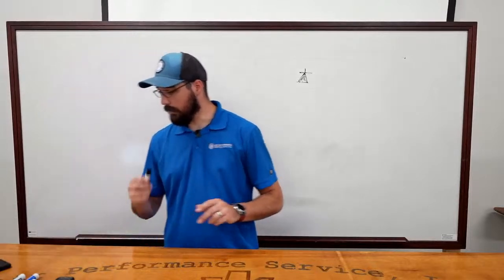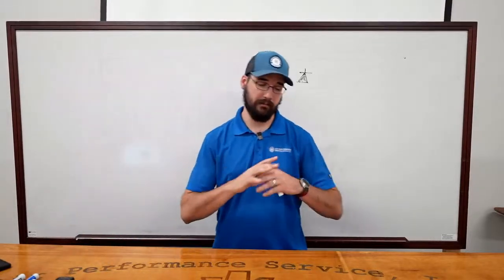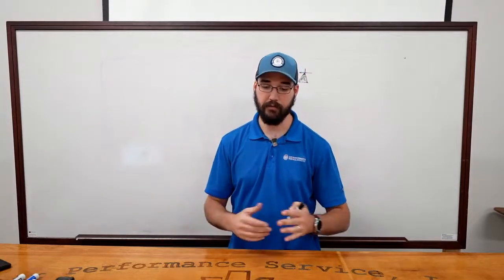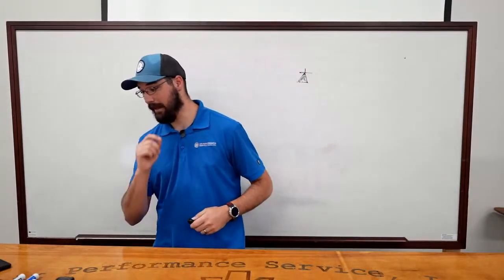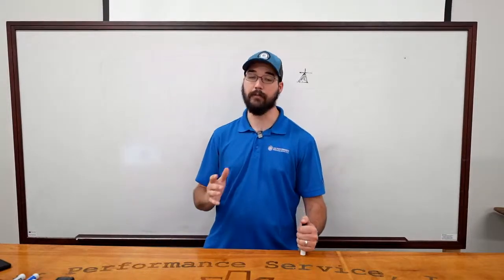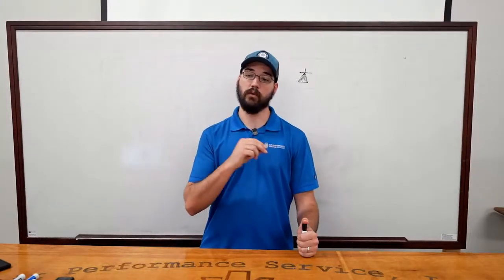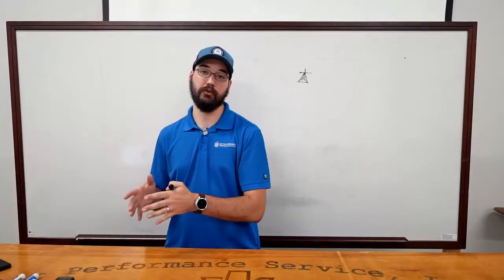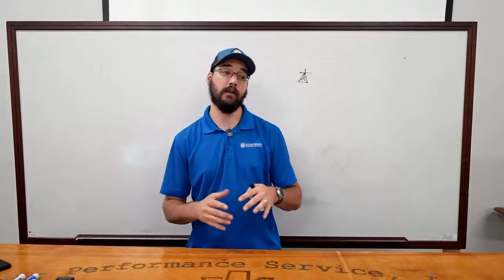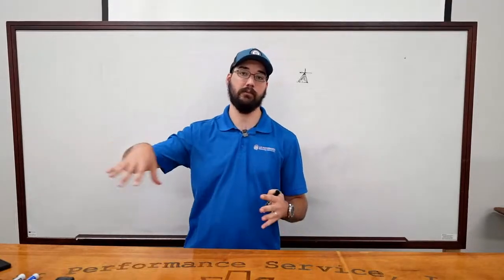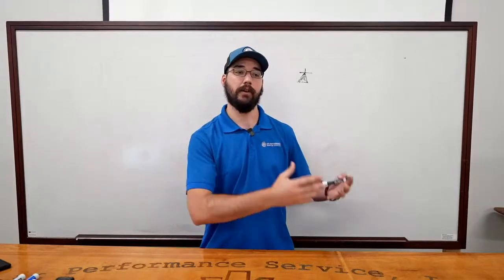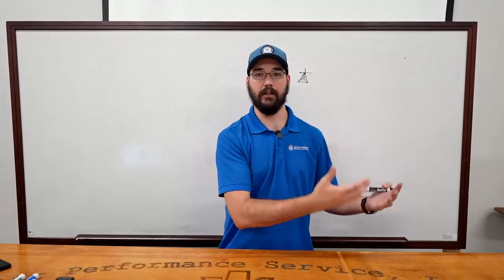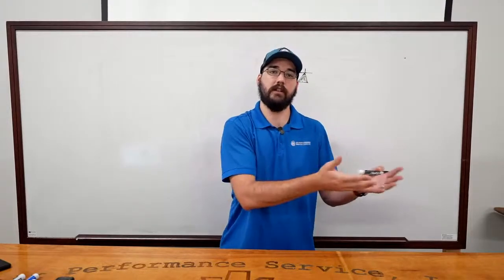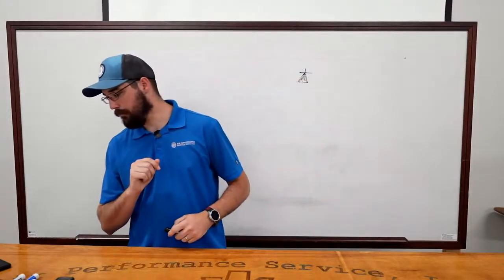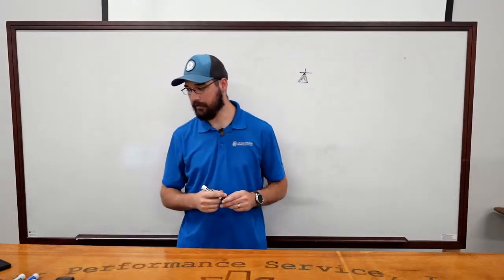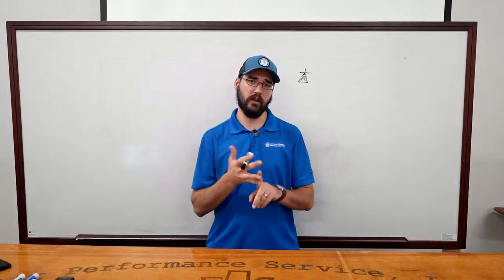Okay. So let's talk about some common faults. The 2 most common, and by far, I'm not going to sit here and go through every fault, but I do want to go through a couple of exercises, and I do want to go through a load charge procedure, what we're looking for, how we're going to troubleshoot that, and then say we're in a critical spot, we need to get this temporarily functioning until we get the leaks and whatever else taken care of. I want to kind of just share my thoughts on doing an active or a live charge on the system just to get them functioning intermediately. So the 2 most common faults that I've personally seen are going to be inverter or current overloads.